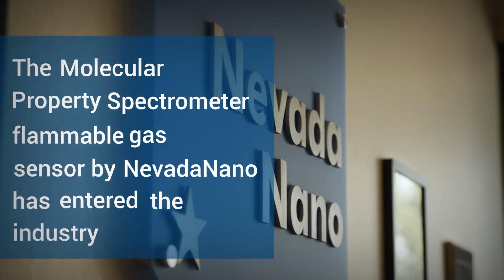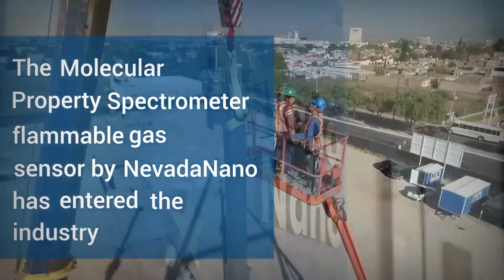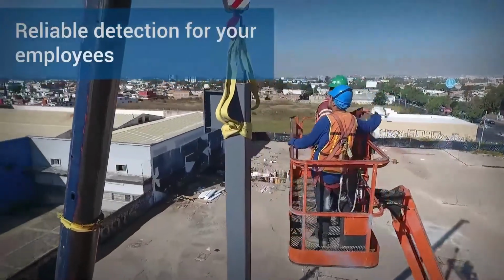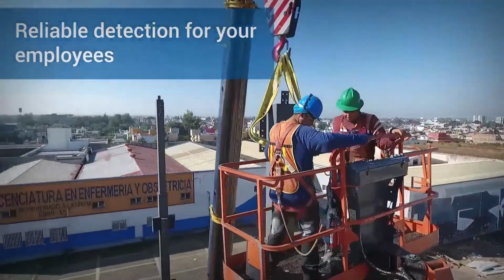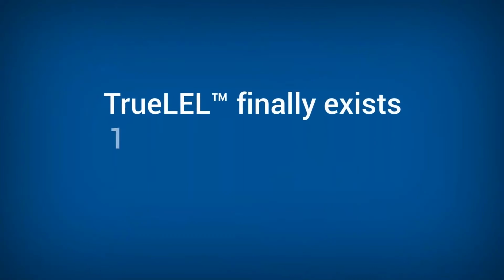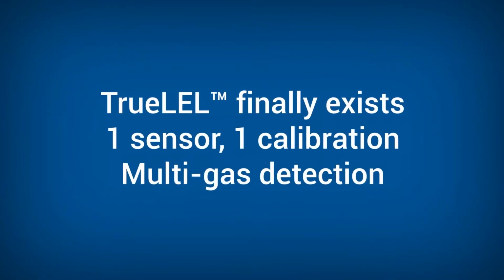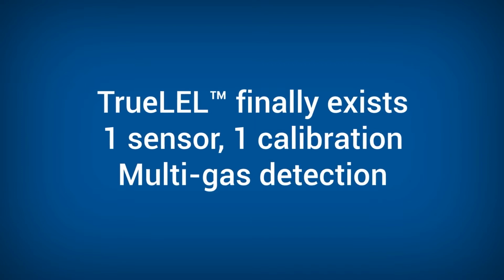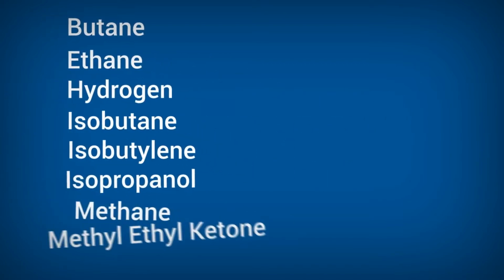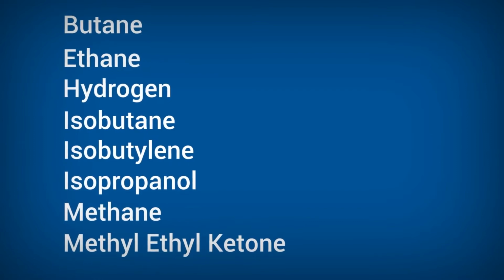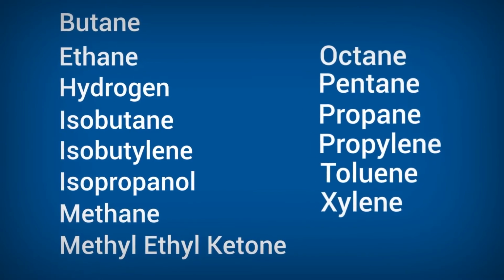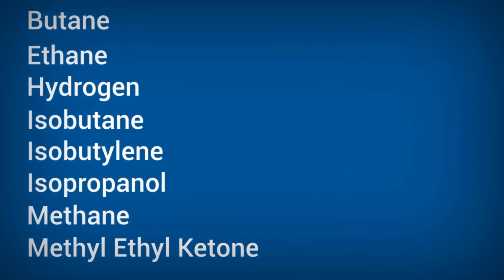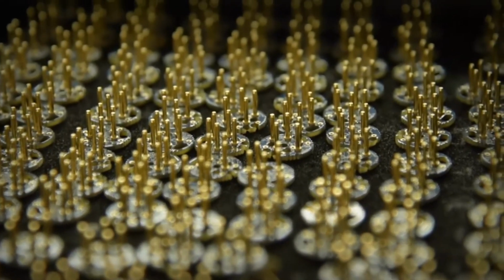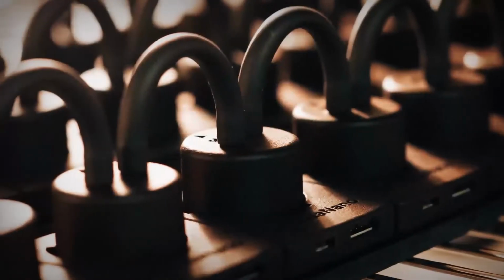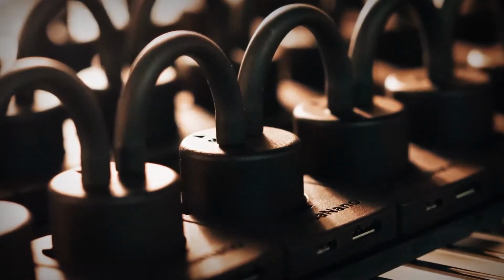The Molecular Property Spectrometer Flammable Gas Sensor by Nevada Nano has entered the industry to disrupt traditional sensor technology and provide reliable detection for your employees. True LEL finally exists. The MPS sensor simultaneously monitors multiple gases with a single sensor, providing accurate indication of the level of combustible gases faster than traditional sensors. The MPS sensor can report 0 to 100% LEL for over a dozen gases and most other hydrocarbons with great accuracy, a feature we call True LEL.